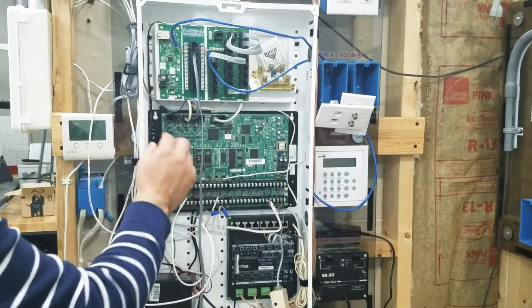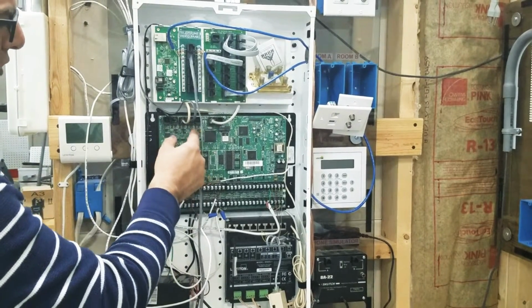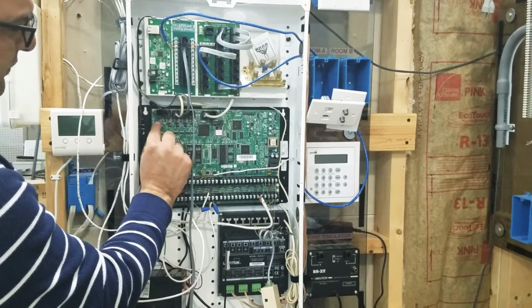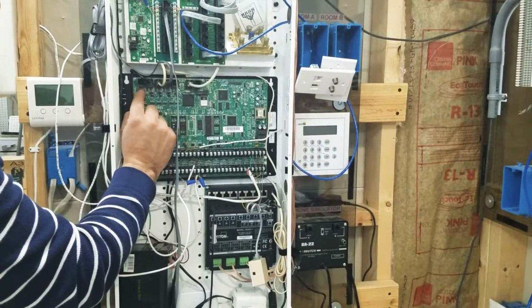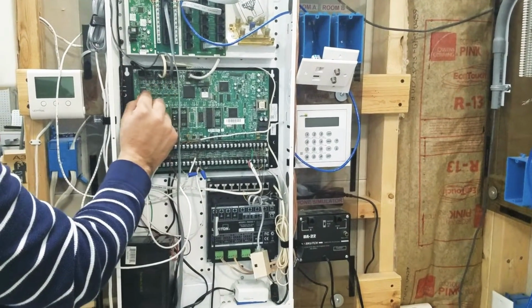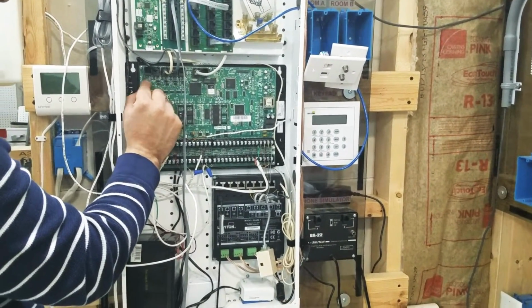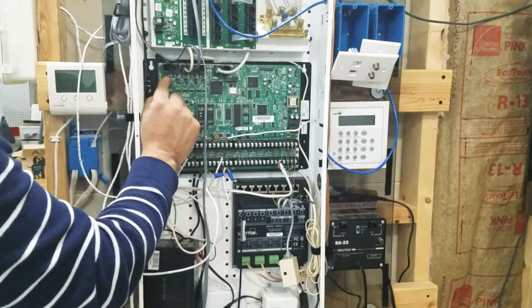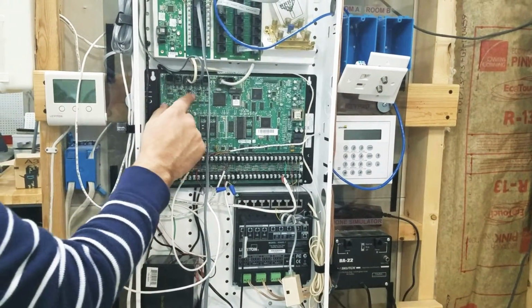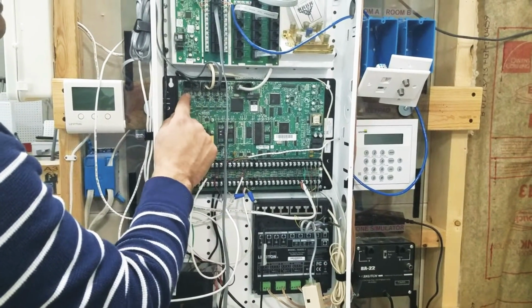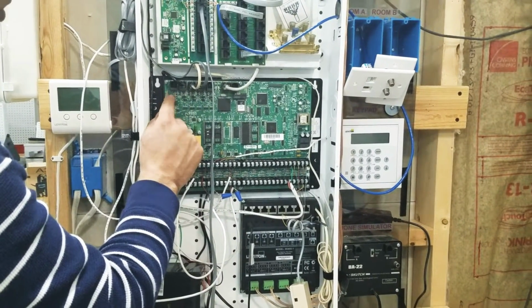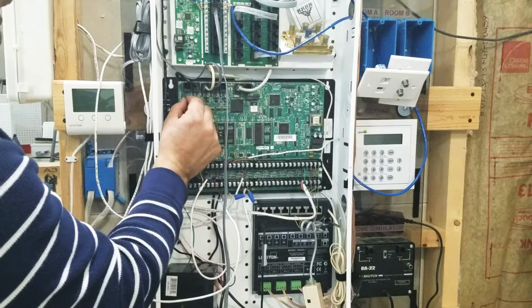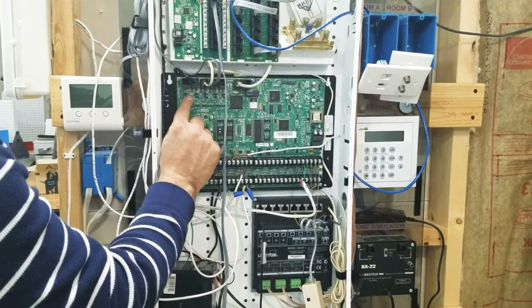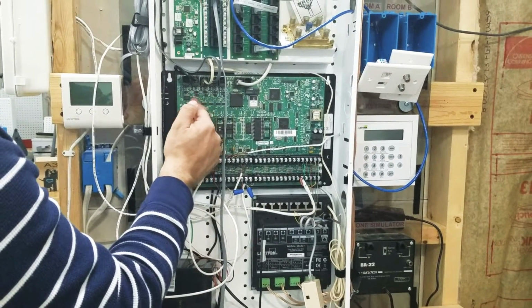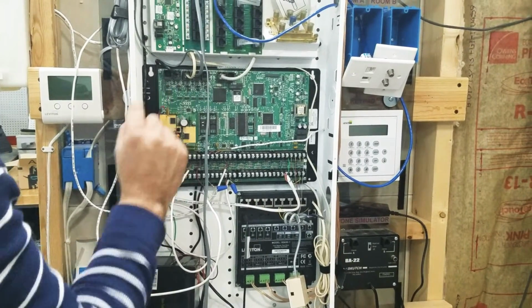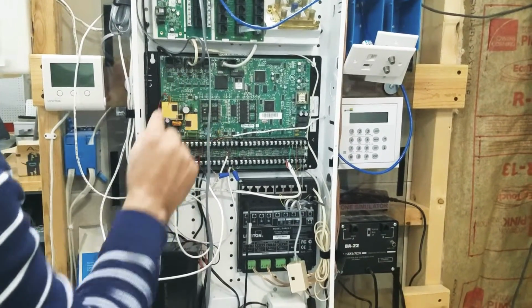If you guys see, what we have here is this bunch of jumpers. If we look closer, this is the RS-232 and RS-485 protocol. So for devices using RS-232, you just take this jumper and put it on the other side, and for devices using RS-485, you take the jumper and put it back. So that's an important point here.